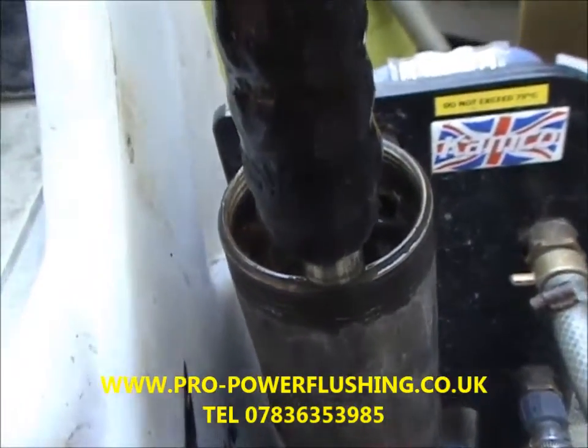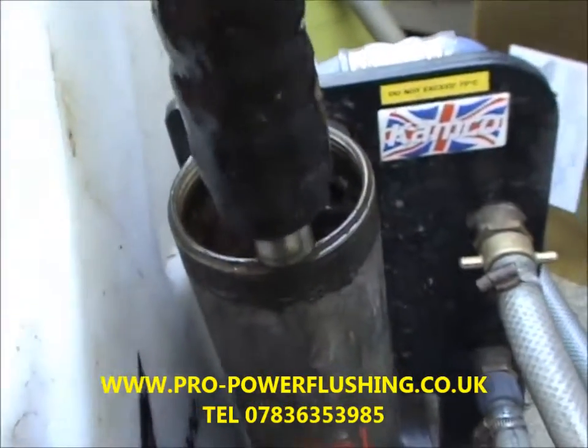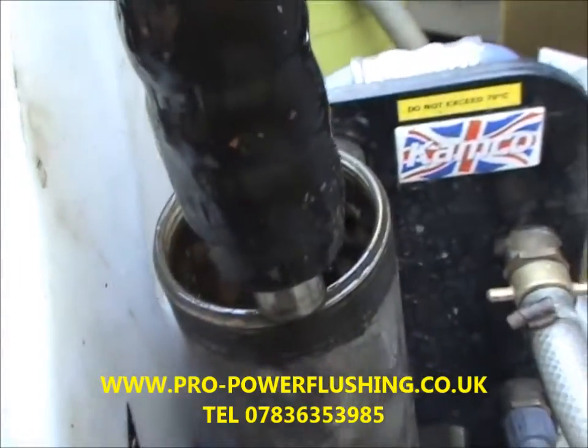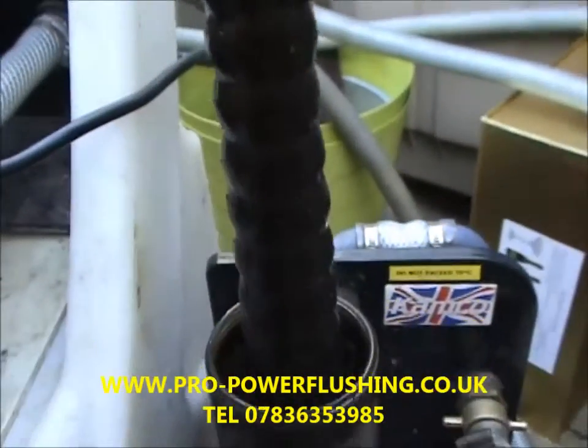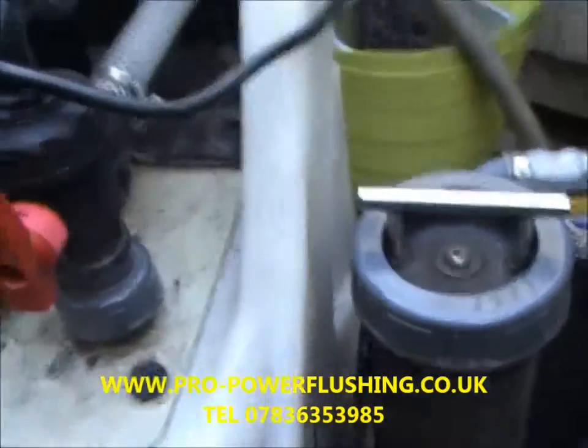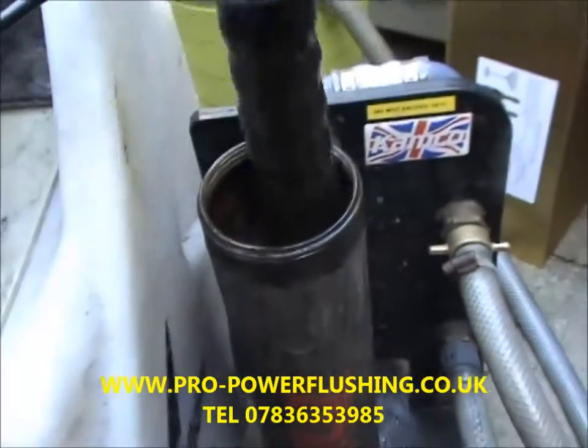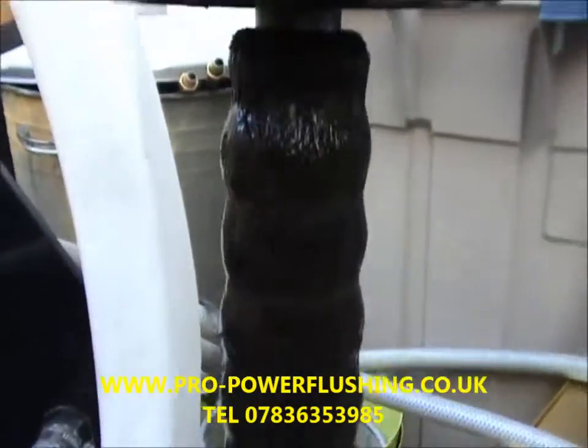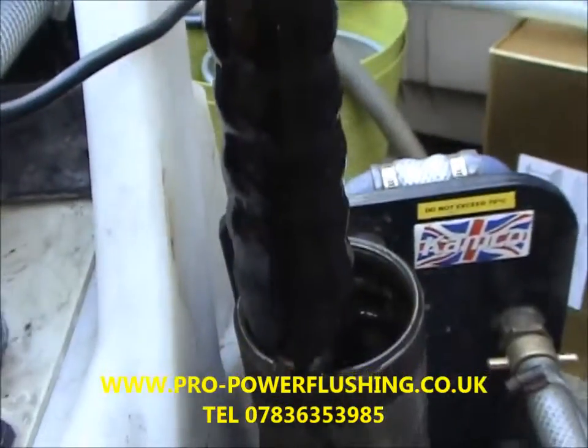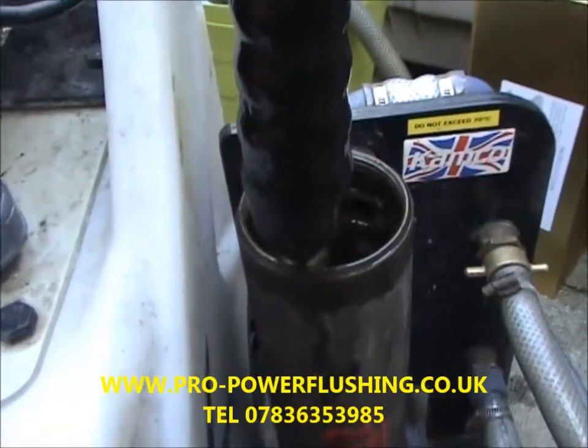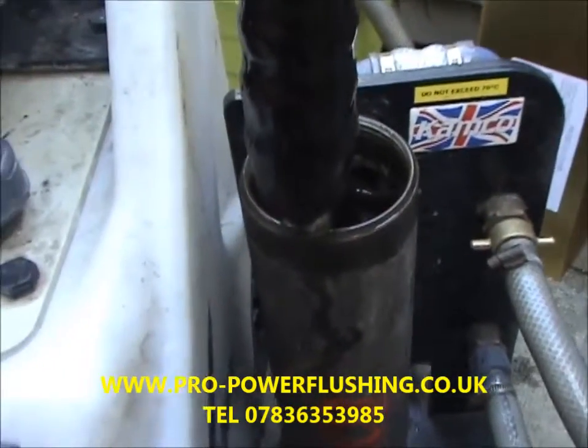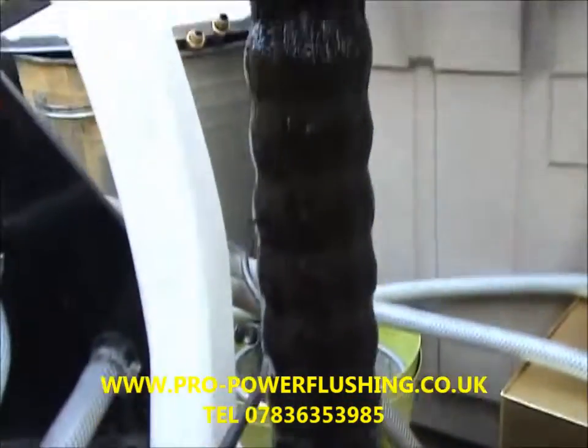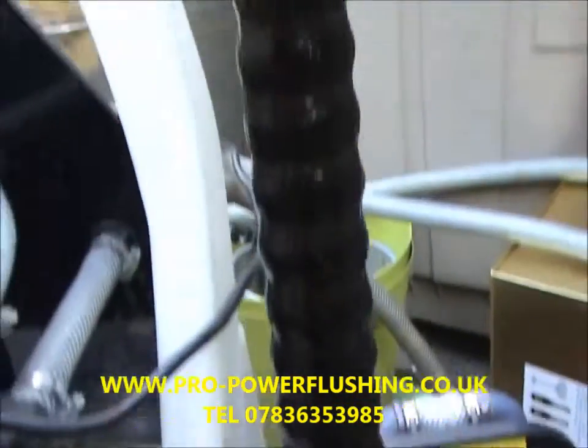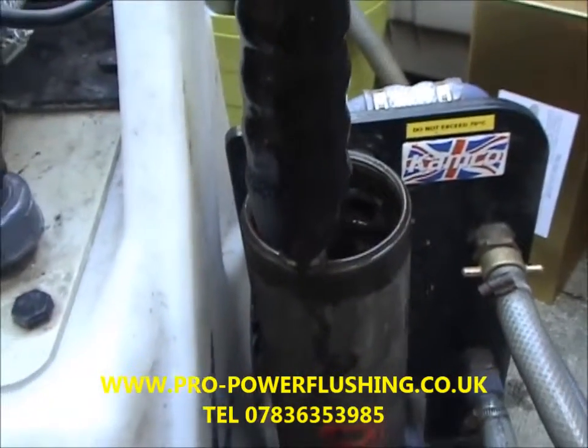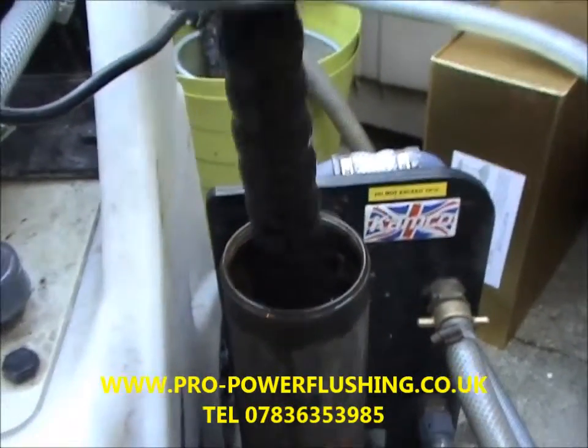So you imagine that going through your pump, your diverter valve, plate heat exchanger. Especially nowadays, combination boilers have got small areas in the plate heat exchanger which can clog up. That running through your pump, eventually it's just going to wreck it, and that's what power flushing is all about. It's about getting all this rust, metal and corrosion out of the central heating system. That would definitely invalidate your warranty if the manufacturer's engineers turned up and found this inside your housing, plate heat exchanger, etc. So the job's going alright. We're going to start the rinsing process soon, and we'll get back to you later.